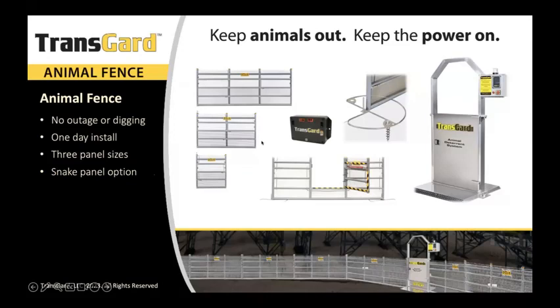We have a snake panel option, typically used in the southern region of the United States where snakes are prevalent. It's a stainless steel perforated option on the lower half of our fence, which prevents a snake a quarter inch or larger from getting through. We've determined, along with animal experts, that anything less than a quarter inch is not going to pose a threat to the substation.